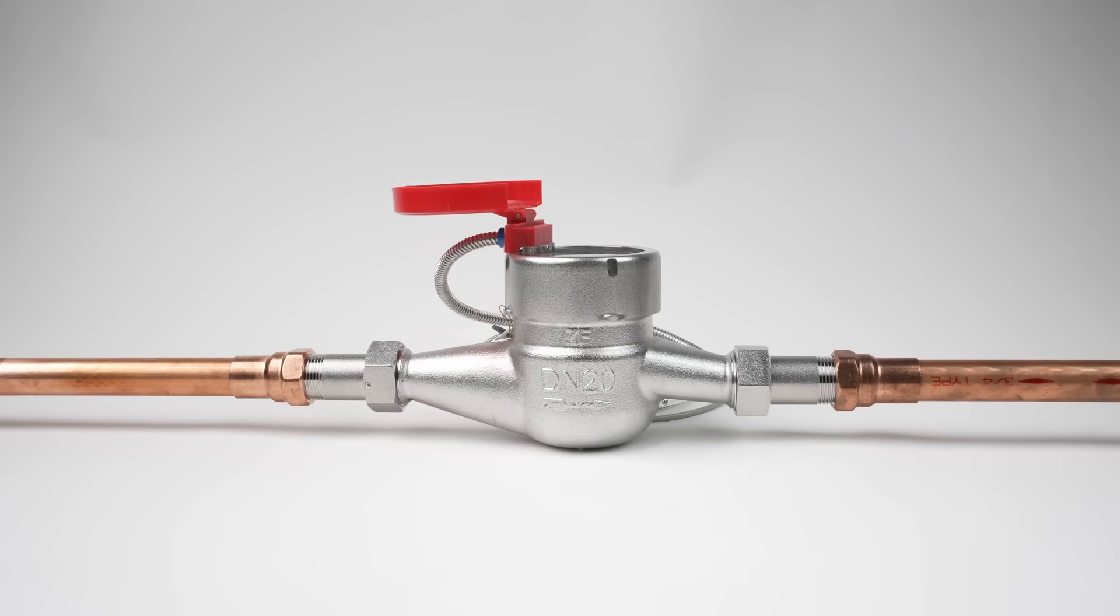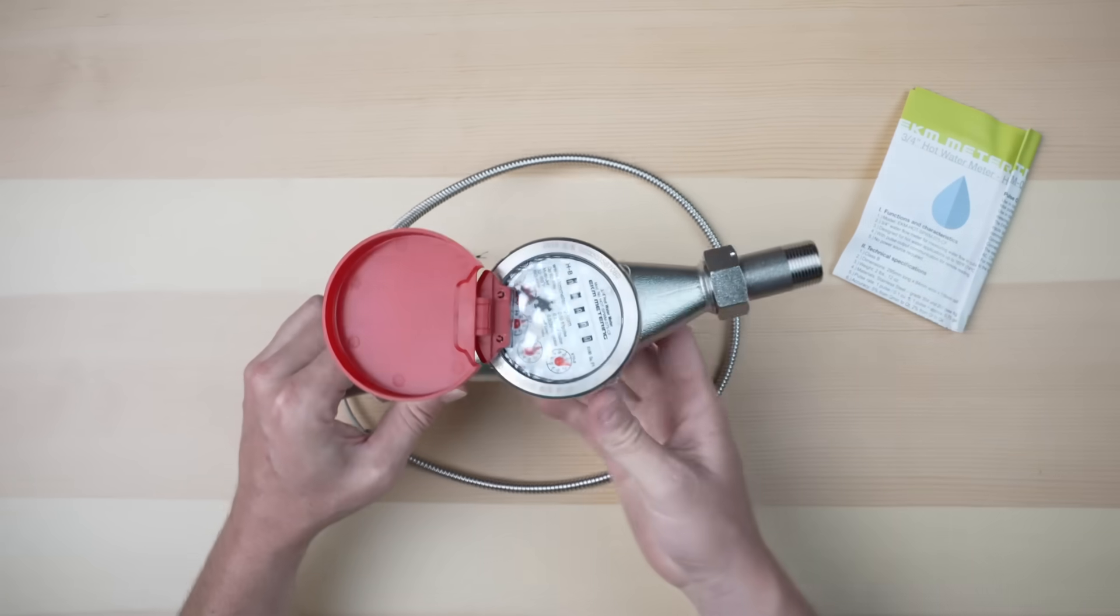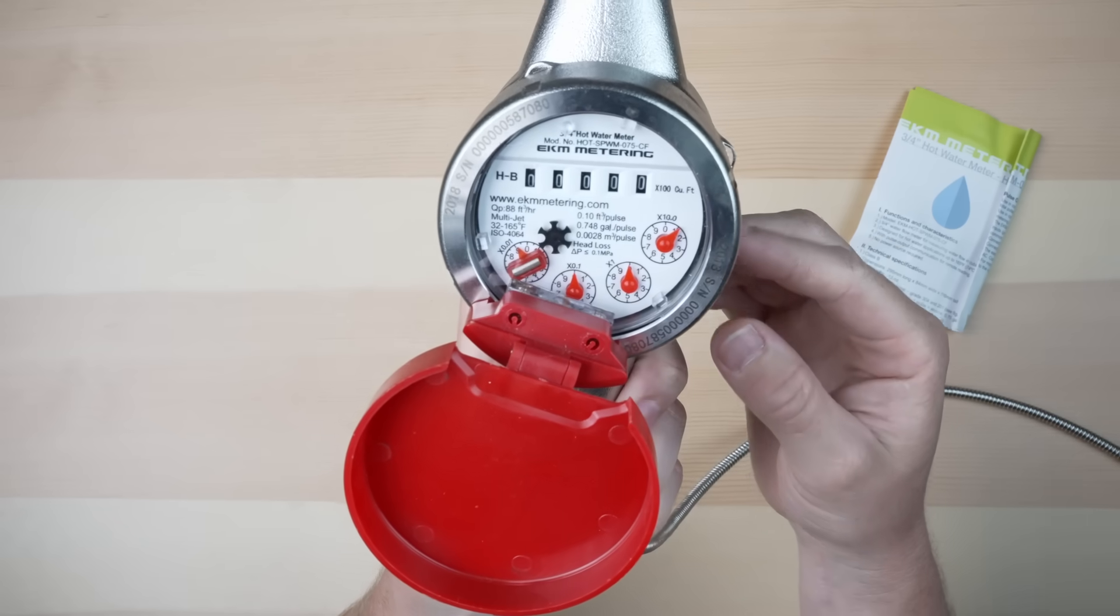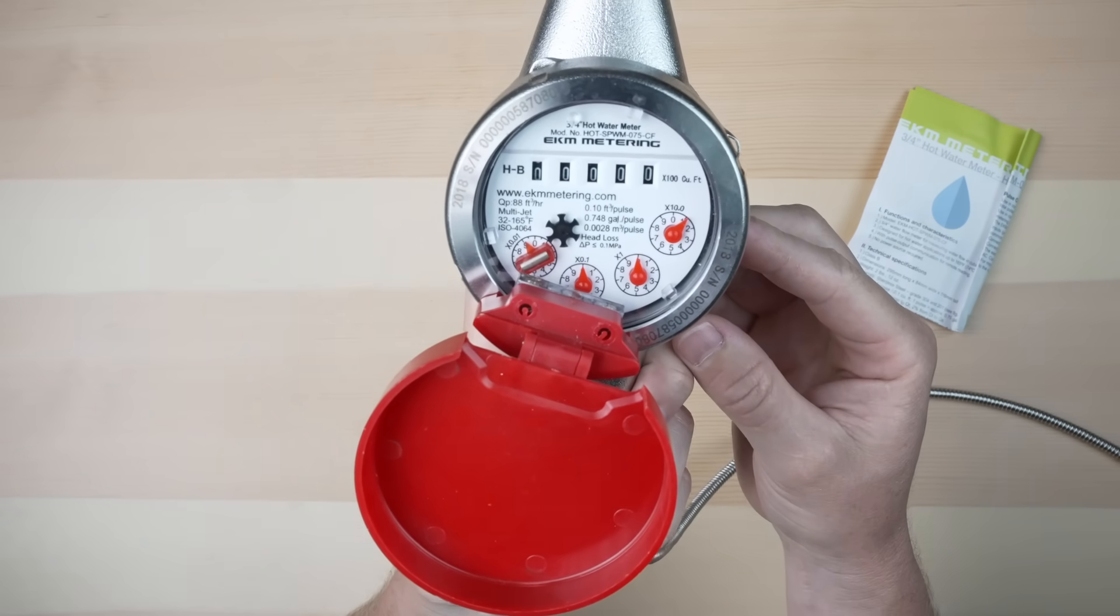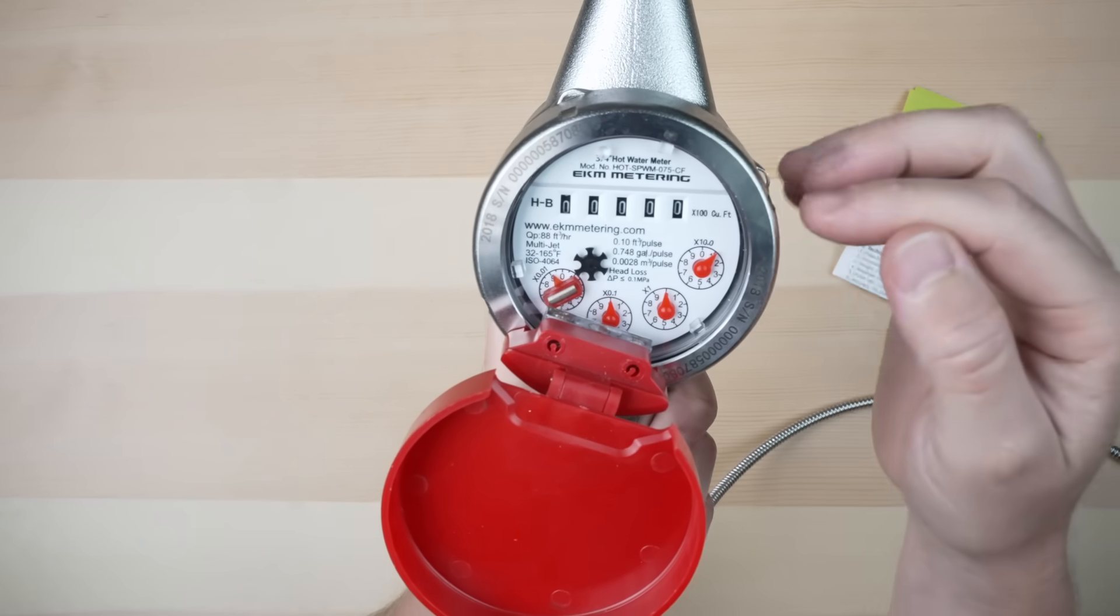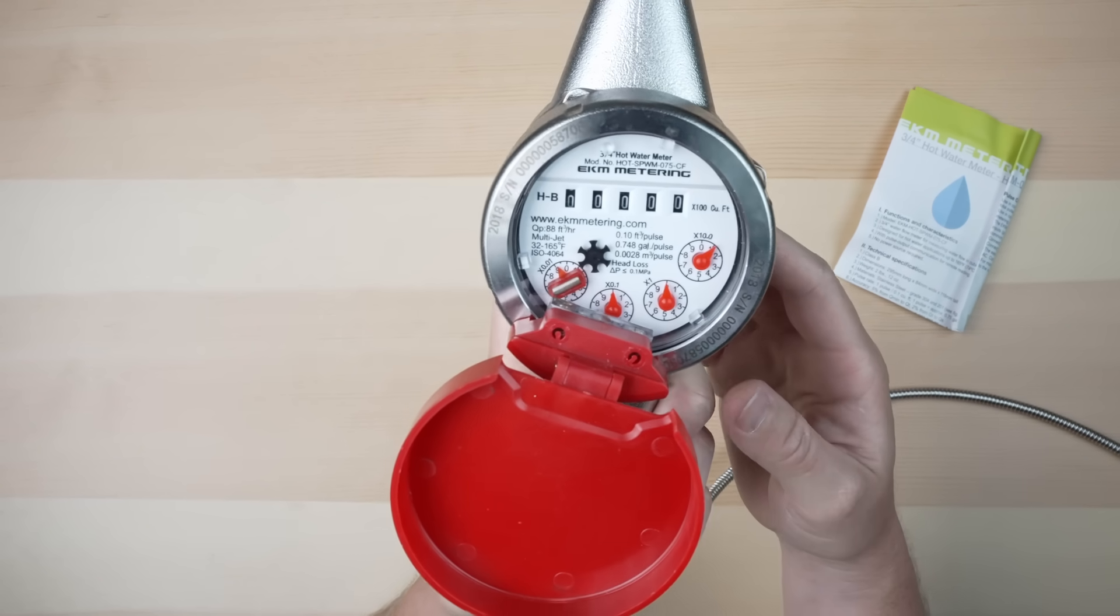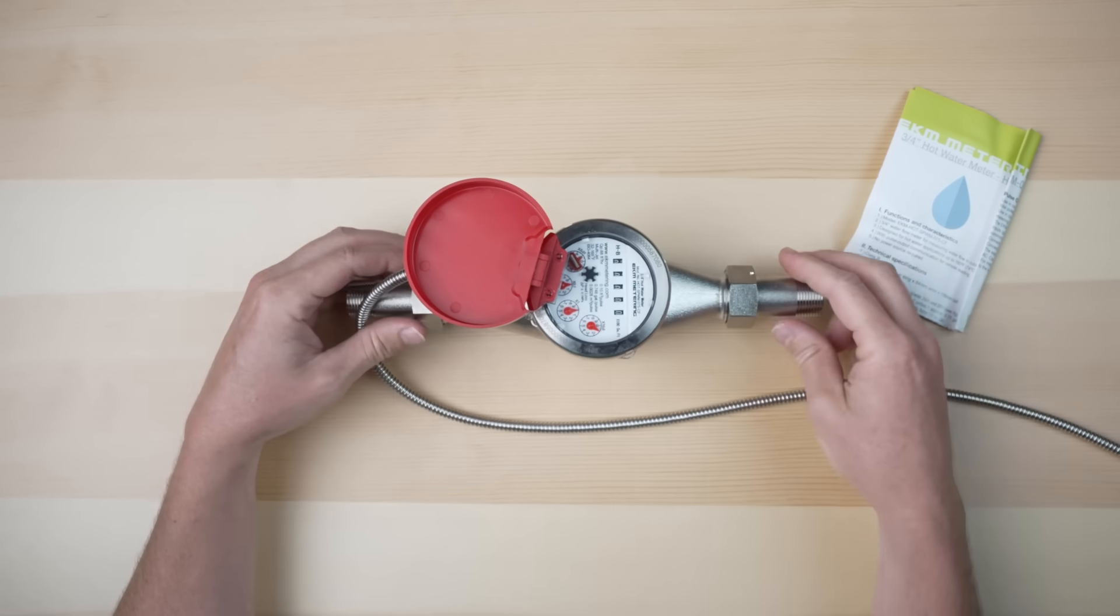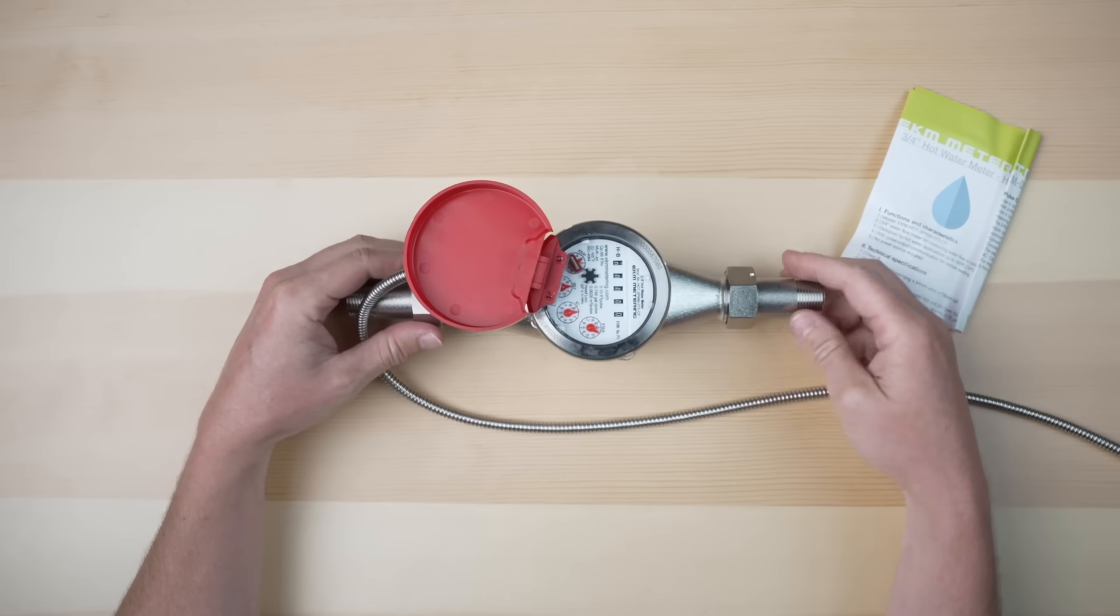The meter reads natively in cubic feet. I can hold it up here to show you the dials. Across the top here are increments of 100 cubic feet. So any number that displays there, you multiply by 100 to calculate the amount of cubic feet. The meter will read 10 million cubic feet before the dials roll back over to zero.